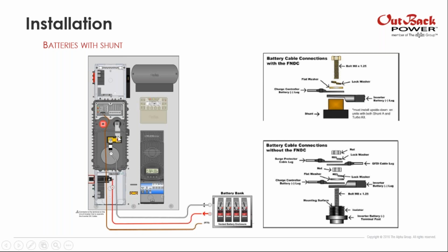This is the shunt. It is joined to the terminal of the inverter by this device, and you will need only to put the positive of the battery bank to the inverter in the breaker of 175 amps for the 48 volt models, and 250 amps for 24 volt models. The negative will come to the shunt in the case of using the FlexNet DC, and if not, directly to the inverter terminal front. And the remote temperature sensor will have its own terminal here in the inverter.